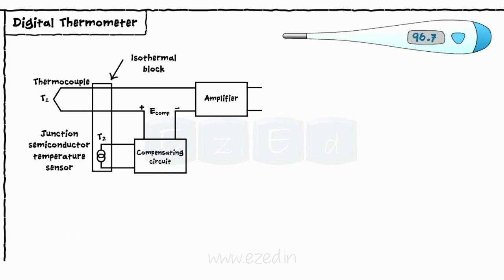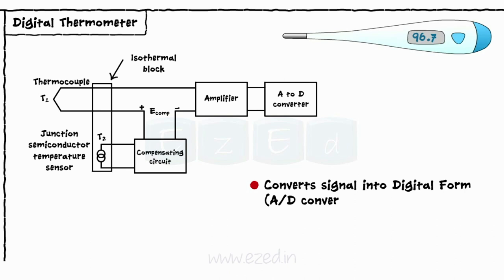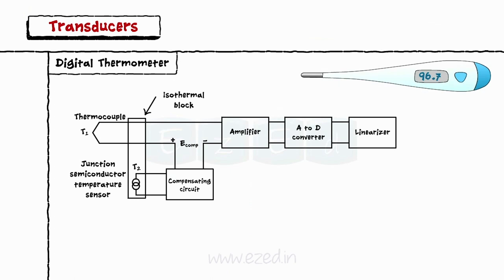This amplified voltage is passed to A to D converter which converts it into digital form. This digital voltage is then linearized by a linearizer and then applied to a digital voltmeter which gives the direct digital display of temperature T1.